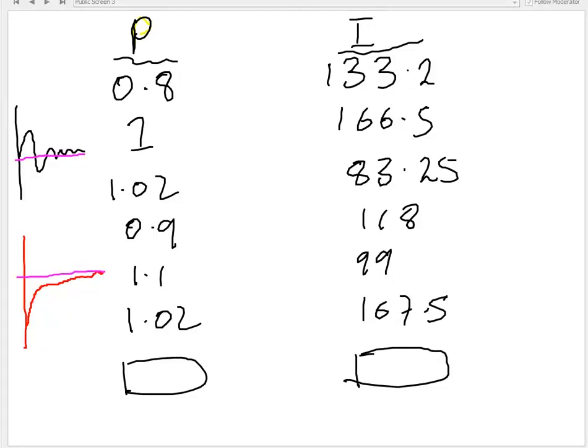These numbers will work. Now, if you put these numbers in and you find that it's a bit over-enthusiastic, it's oscillating, all you do is just halve whatever you found as your P term. If you stick these numbers in and you find it's just a little bit slow, you just double your P term. What that means is, although I calculated this to be 0.8, it could easily be 0.4. And it could just as easily be 1.6.